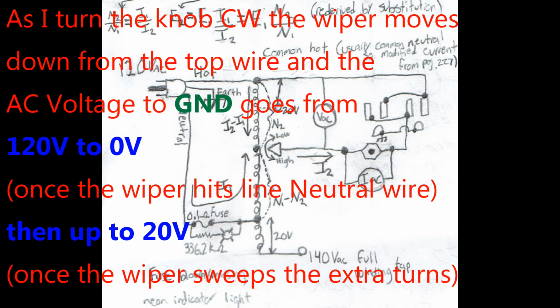As I turn the knob clockwise for the Variac, the wiper starts to move from the top of the page down towards the middle, and the AC voltage to ground in the wiper goes from 120 volts down to 0 volts. It reaches 0 volts once the wiper hits the actual line neutral wire that's coming in from the wall. Once I continue to turn it a little bit past that, the voltage then will travel back up to 20 volts once the wiper sweeps across those extra turns at the bottom.